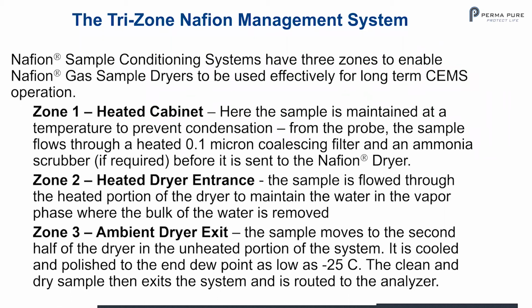In zone 2, the heated dryer entrance, the sample flows through the heated portion of the dryer to maintain the water in the vapor phase, and here is where the bulk of the water is removed. In zone 3, your ambient dryer exit, the sample moves to the second half of the dryer, the unheated portion of the system. It is cooled and polished to an end dew point as low as minus 25 degrees C. The clean and dry sample then exits the system and is routed to the analyzer.